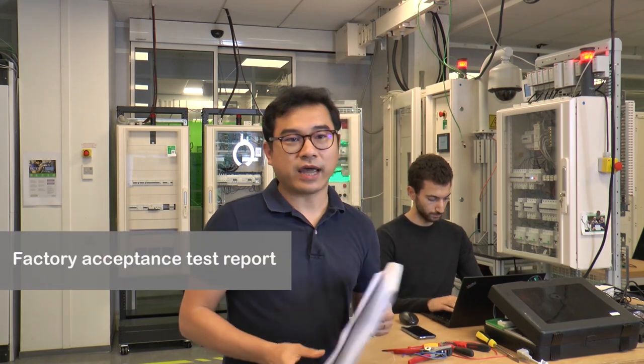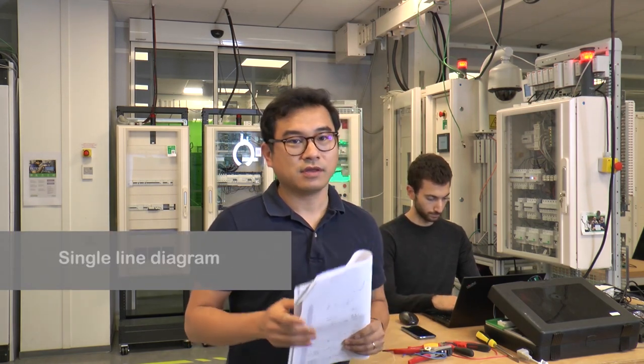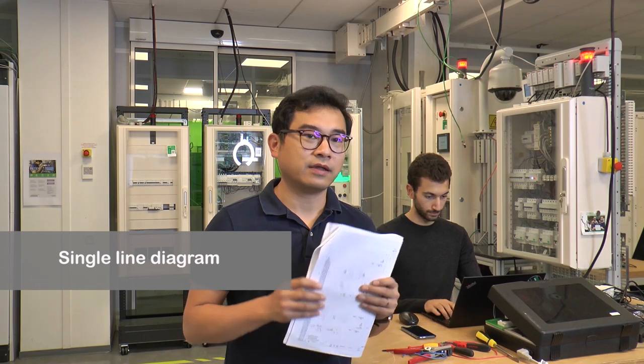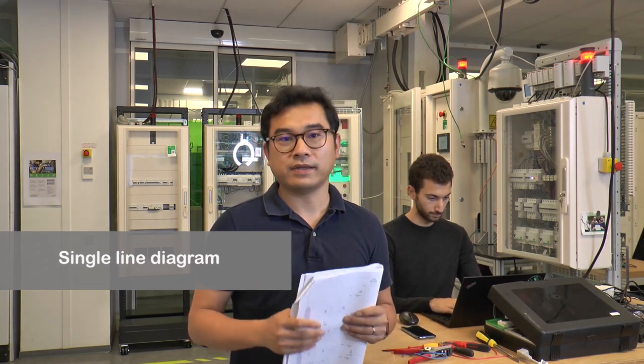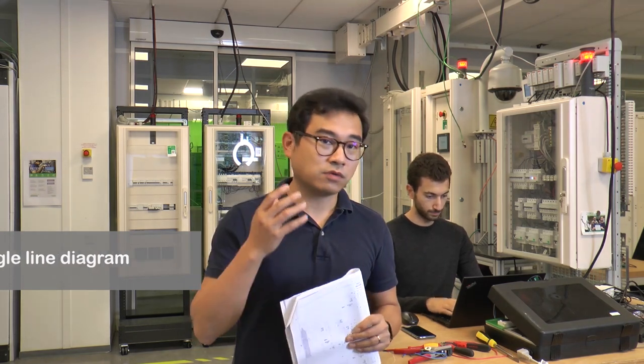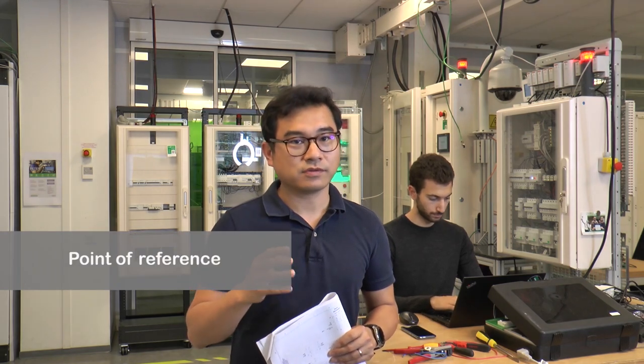The panel builder plays a vital role during an electrical installation project, from mechanically assembling the panel to making sure that all the complicated wiring and communication are implemented correctly and fully tested before shipping to the end user. In addition, handing over factory acceptance test reports, drawings, and single line diagram to the contractor and end user is not only required by the electrical installation standards, but also the best way to demonstrate the work has been completed. It also provides a useful point of reference for the entire life cycle of an electrical panel.